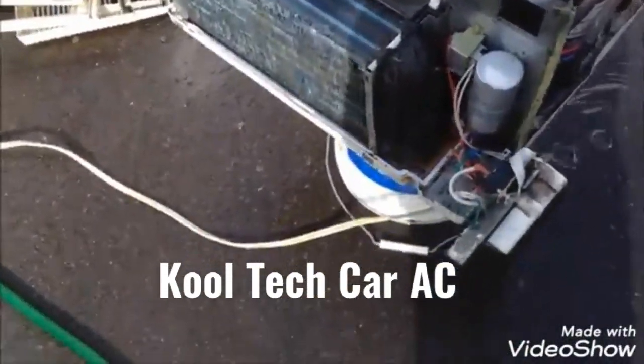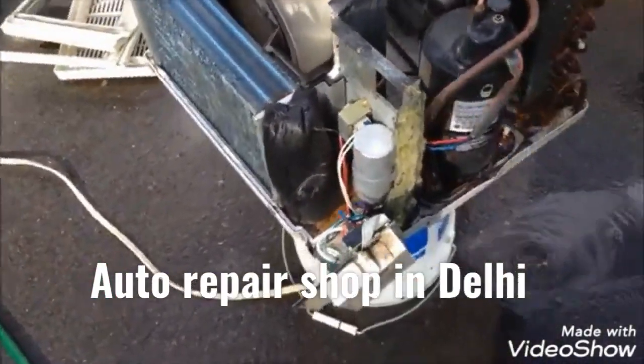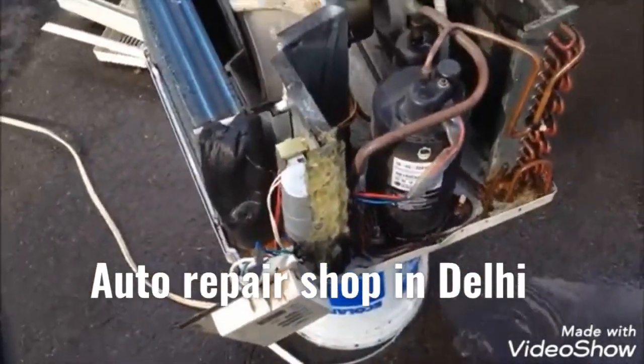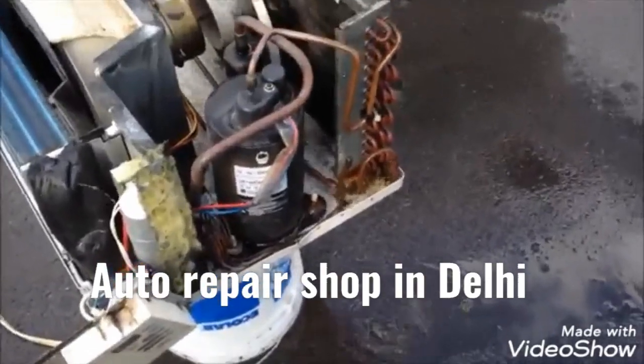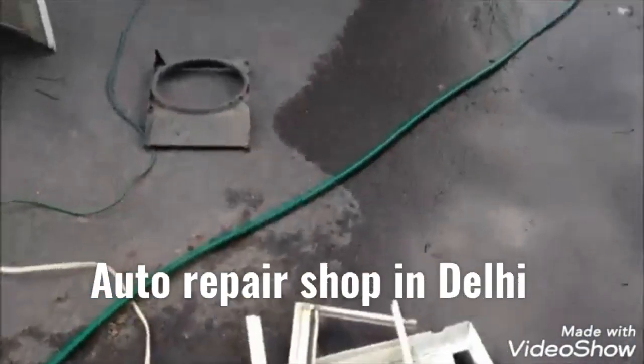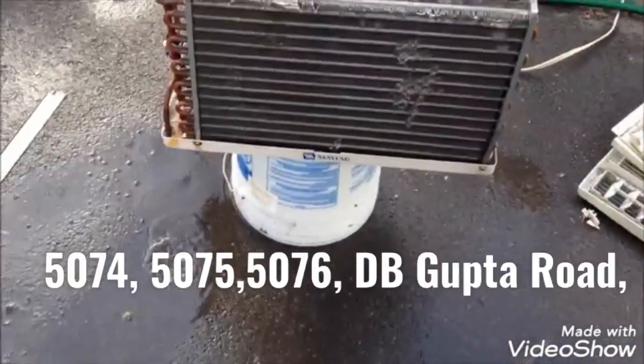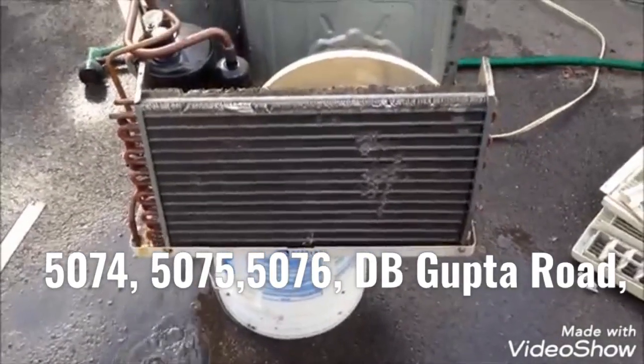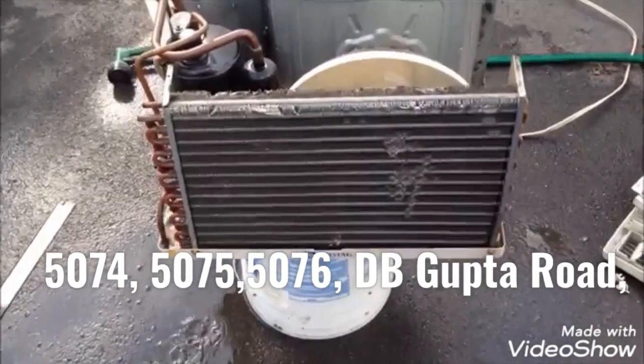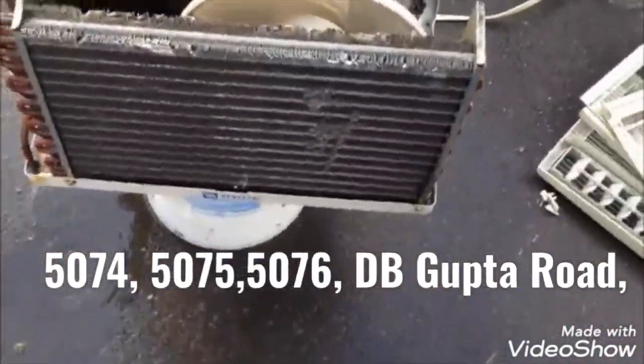The evaporator's clean now. I've never seen that much dirt build up in an evaporator either. Where it was unhappy before, now I just think it's kind of wet and unhappy. Didn't get the controls wet though, so I'm not worried about that. I can't put that back in because it rubs too much, so it's not going to have proper heat rejection — it'll wear on the compressor pretty bad. But it's not even that old, it's got digital controls and everything.